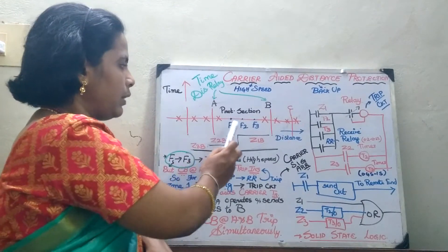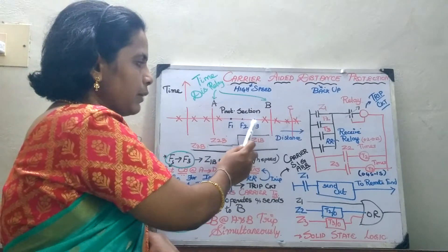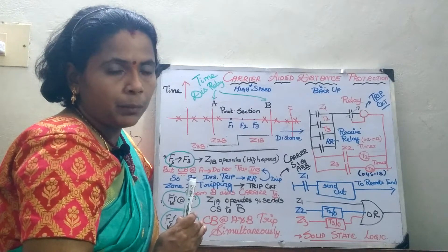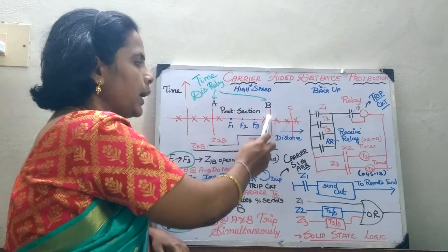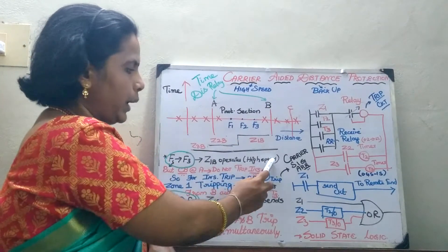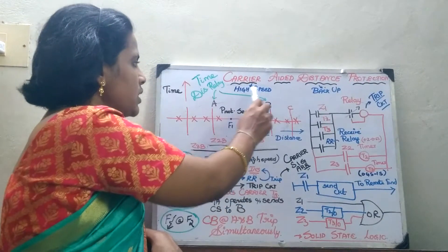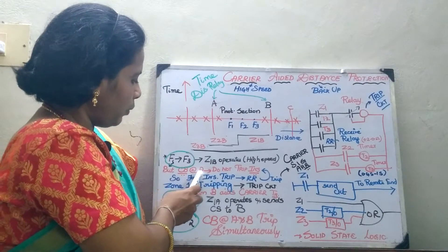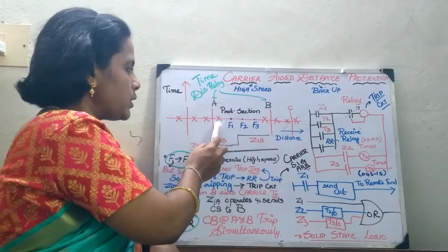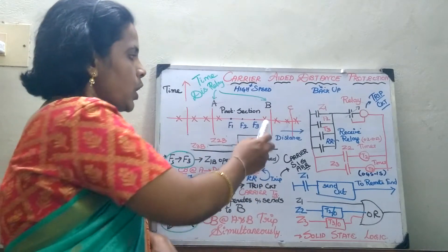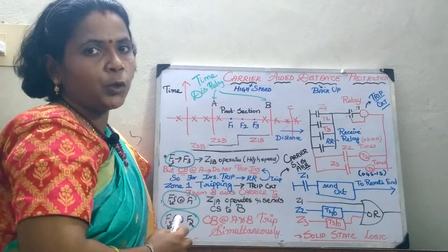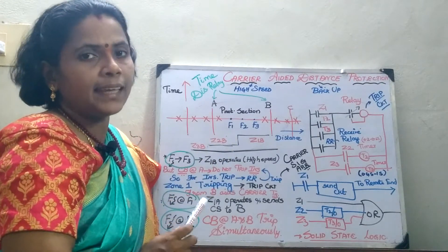For a fault at F3, we will consider all three points. Suppose a fault occurs at F3 — immediately the breaker at B will open to isolate the faulty section. But carrier protection requires that breakers at both ends A and B should open. Whenever a fault occurs at F3, the nearer relay at B will open immediately, facilitating high speed operation. However, the circuit breaker at A does not trip instantaneously. Once the breaker at B opens, it will send a carrier receive signal to A so as to open the circuit breaker at A, thereby facilitating carrier current protection.